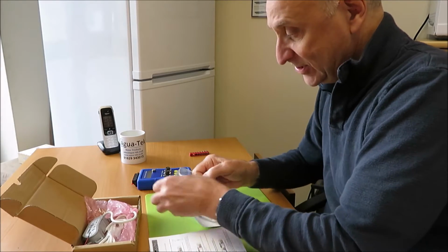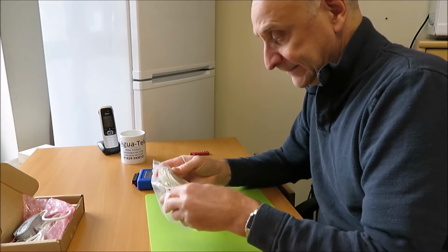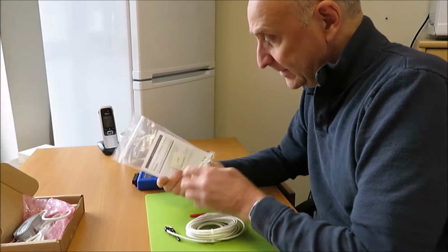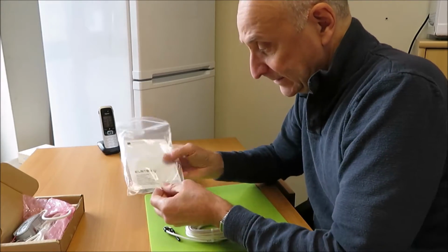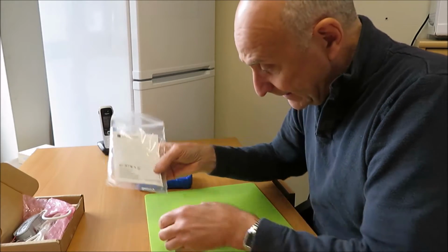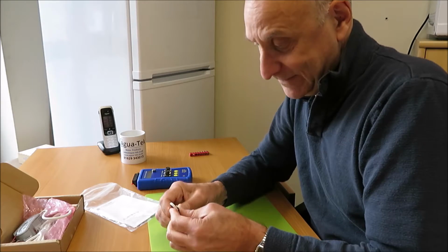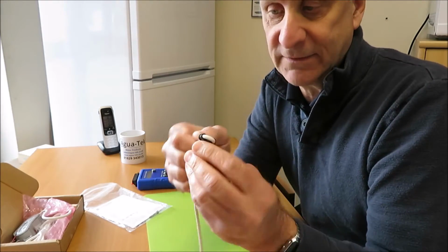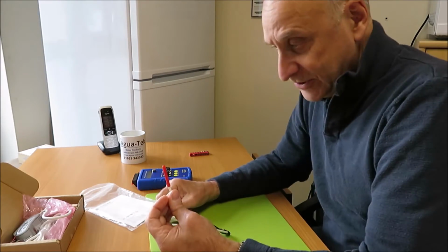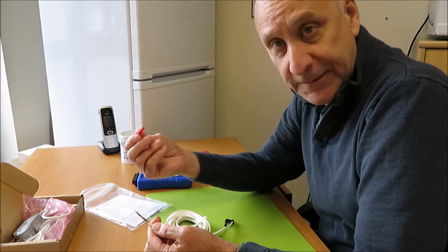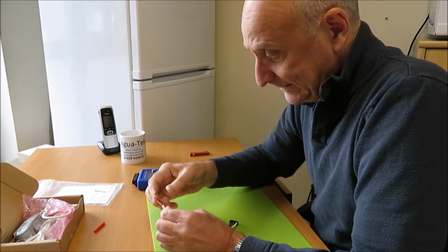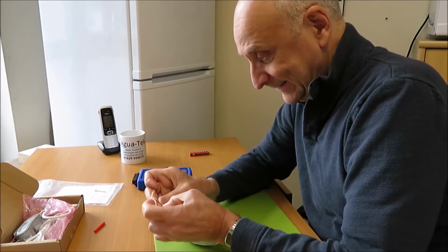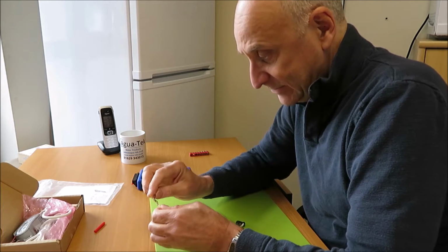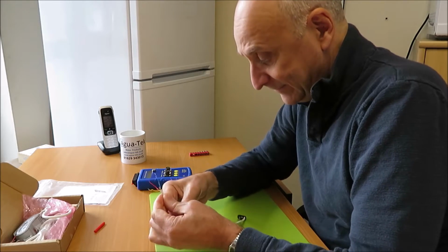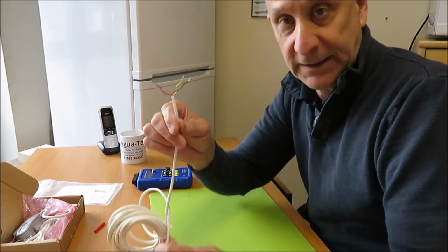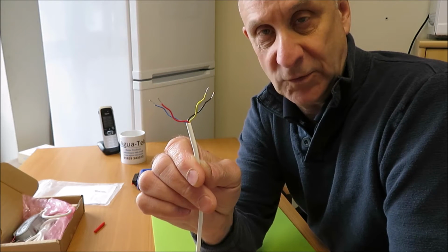Both flow sensors obviously come in their own packets. This is the T-Probe type. It has a little screw which I will leave in the bag, which actually inserts once being fitted onto the water meter itself. There's a little hole, I don't know whether you can see it very well there, but we have the cables which are enclosed in a rubber sheath. Remove that, and then if I undo these little wires, you can see that we have a selection of wires, two of which will have the signal coming from the flow sensor itself, and there's the 4 different wires.